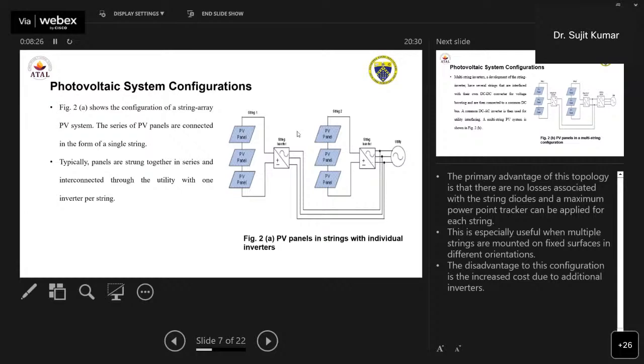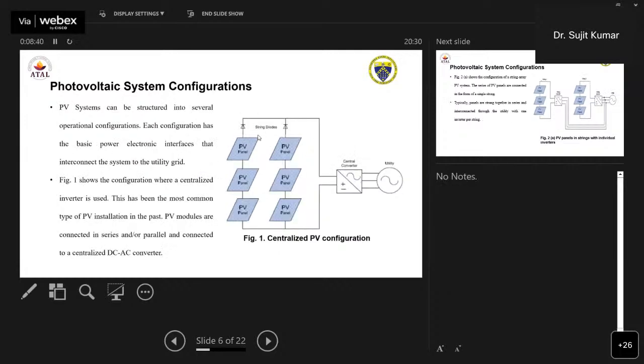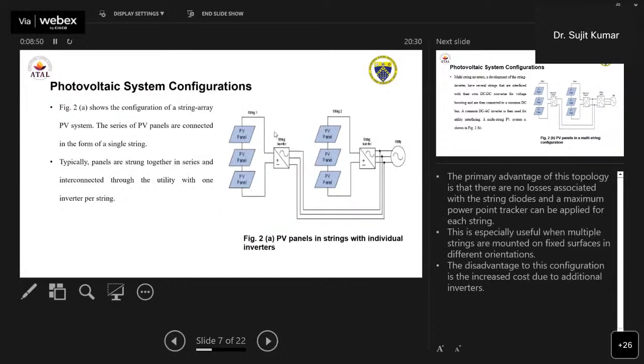So what is the primary advantage of separating the single string with the individual inverter? The primary advantage of this topology is that there are no losses associated with the string diodes. Because if you see here, there are string diodes, which are unidirectional, so that the leakage currents cannot come back to the solar. Here that problem is avoided. And the maximum power point tracker can be applied for each string. This is especially useful when the multiple strings are mounted on a fixed surface in different orientations. This is the best way to use multiple strings with individual inverters.